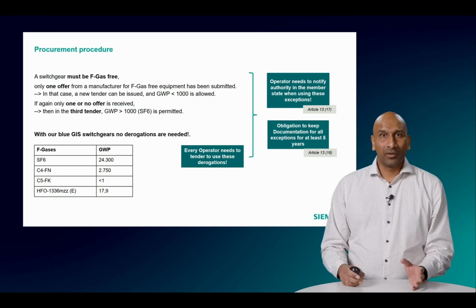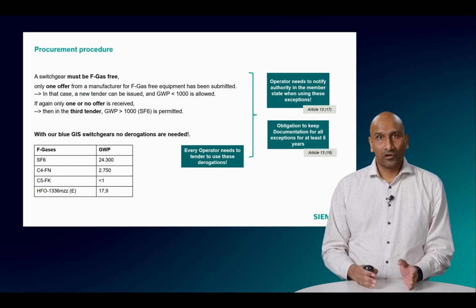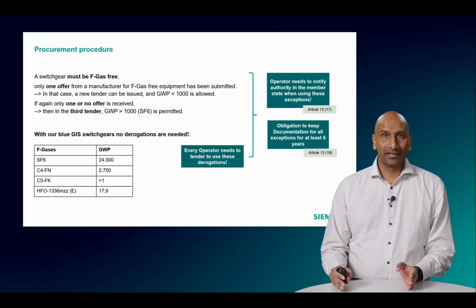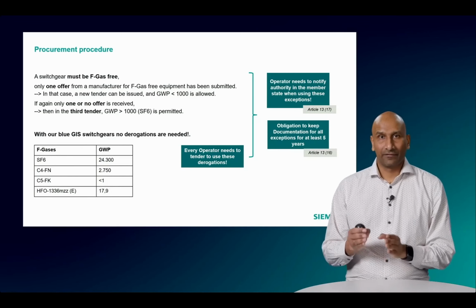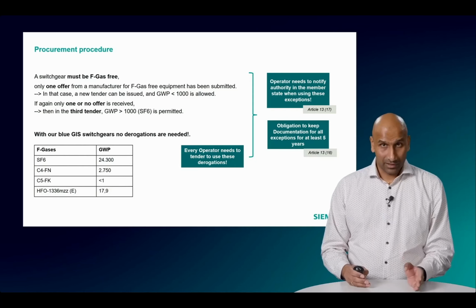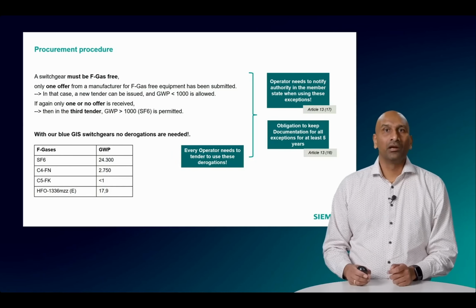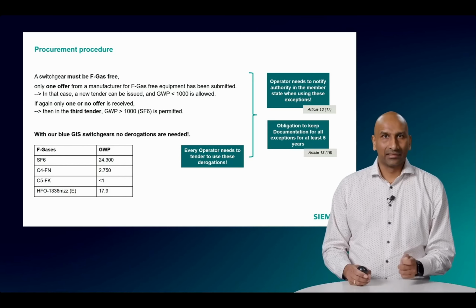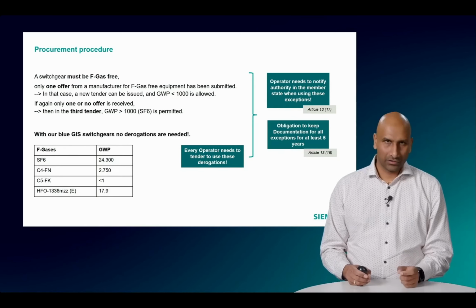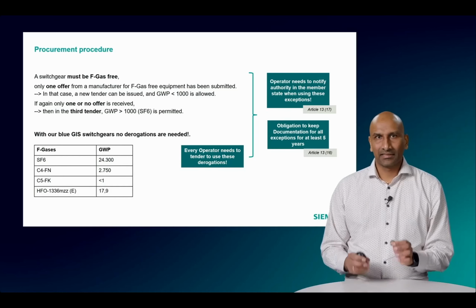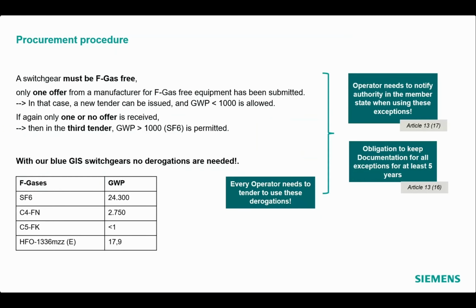Another important part is the procurement procedure. The regulation also outlines specific procurement guidelines to ensure market readiness for F-gas free switchgear. Starting from 2026, any 24 kV switchgear must be F-gas free unless there is only one manufacturer offering such a solution. In that case, a second procurement round allows equipment with a global warming potential below 1,000. If no additional offers are received, a third tender round may permit equipment with a GWP above 1,000, which also includes SF6-based solutions.